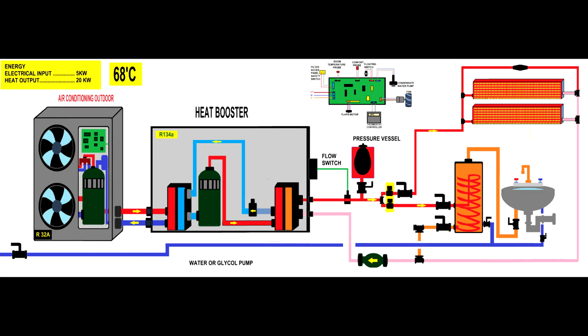So this system has on the left hand side the outdoor, and on the right hand side you have the heat booster. If you don't use the heat booster, it will still work with only one plate heat exchanger, but you will not get 68 degrees Celsius. You will bring it up to probably 40 to 45. Let's say if you design a crazy system, you might reach up to 50, but that will be very hard.